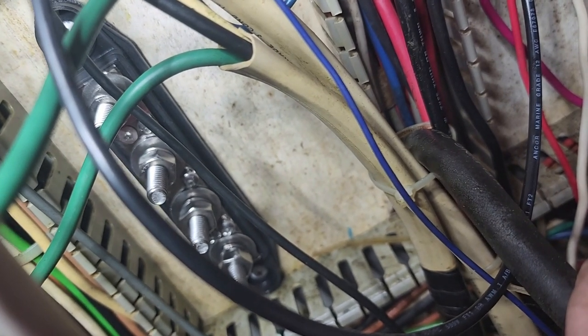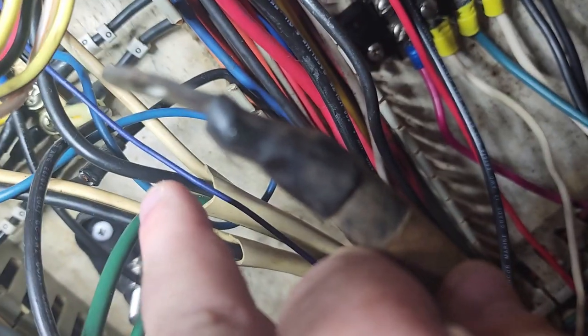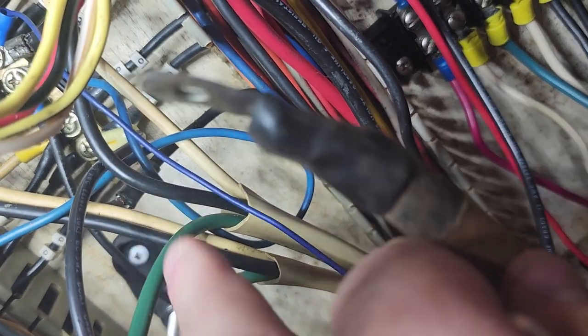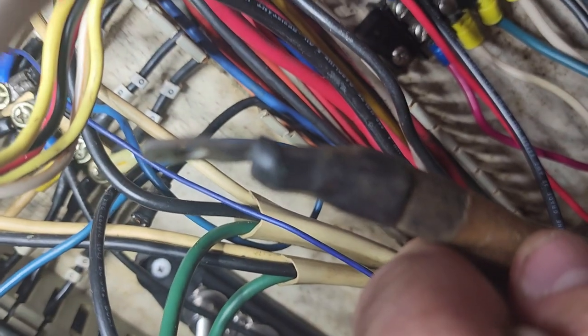that main bus bar. So eventually I'm going to either run a new cable or cut this off and re-terminate it, and it's gonna go to that one right there, and then from that one back to that one, and probably another one next to it, so that there's just way too many. I've already removed like six grounds that were no longer used. So I'm just working our way through this.